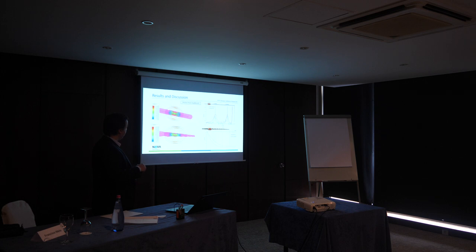Here we can see the wire with the circular constant radius cross-section, and here we can see the endodontic file with a defect. For the numerical simulation, the defects were detected for the wire, but for the endodontic file, it was not, confirming the experimental values that we determined previously. Also, for the differential probe, the results were similar. So typically, we can detect the defects in the wire with a circular cross-section, but not with the endodontic file with the conical shape that defines the instrument.